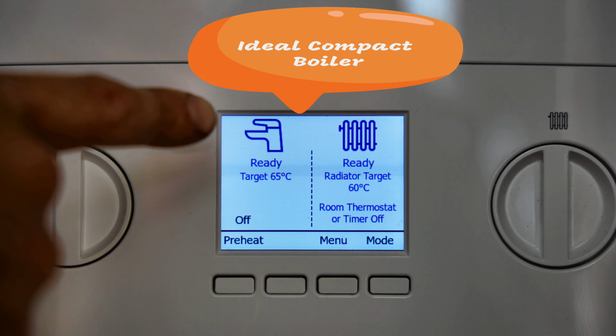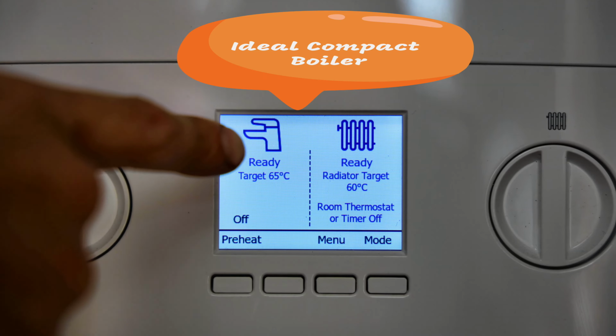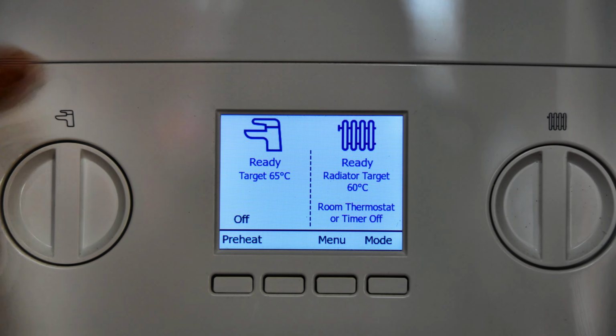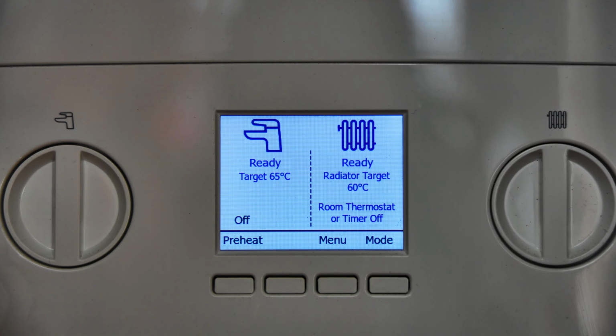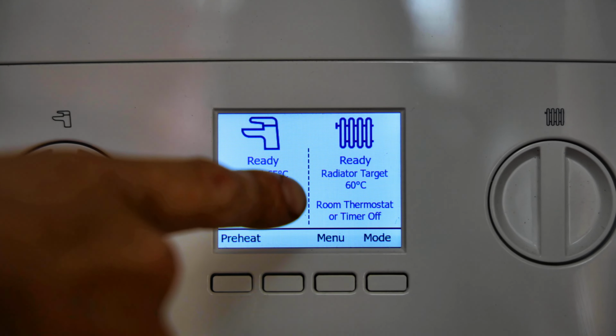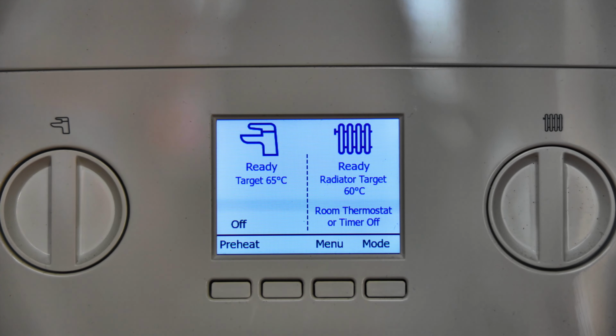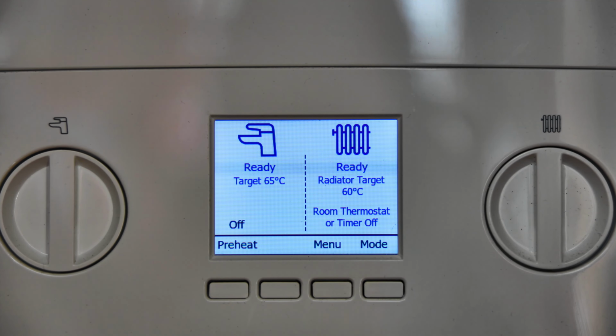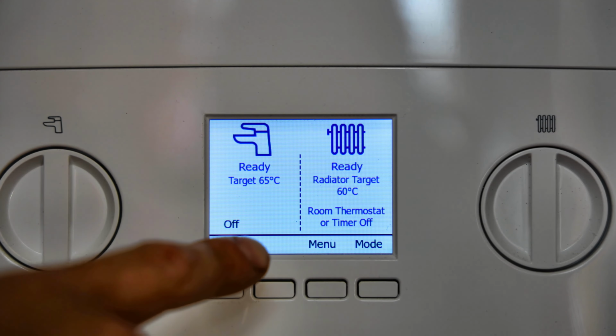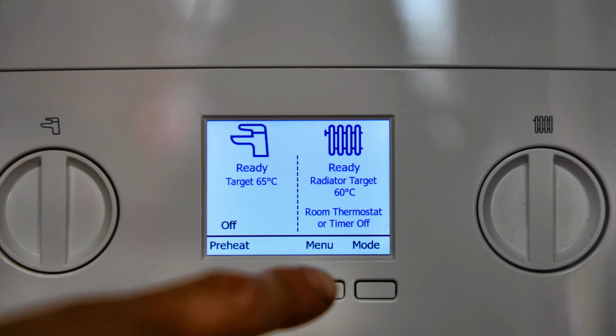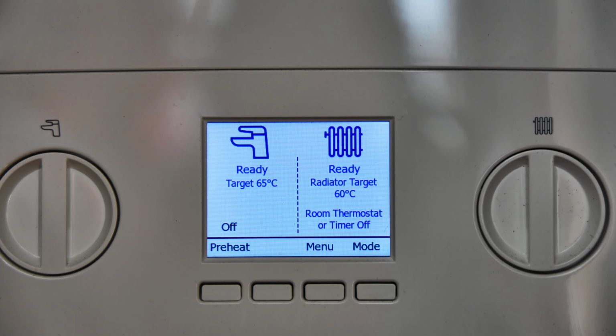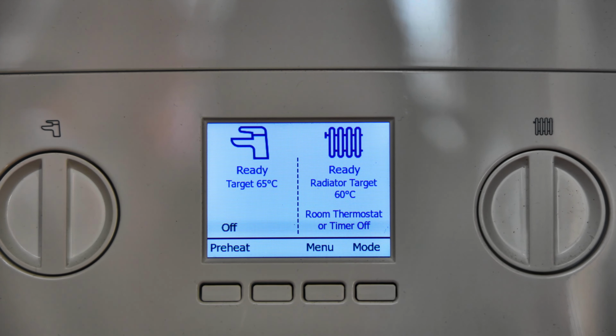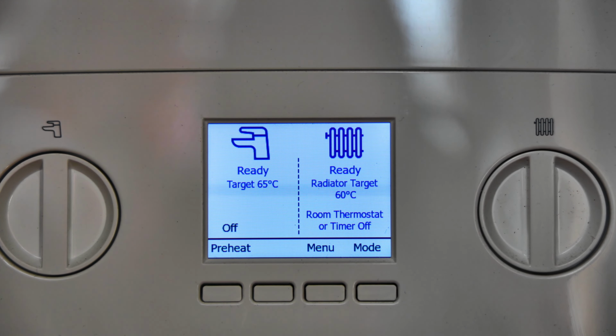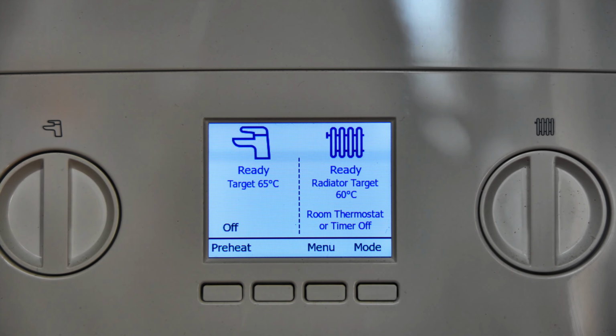And then on the right hand side, that's the radiator symbol, which says ready, meaning that the room heating at the moment is off. And then the radiator target temperature is 60 Celsius. So that's actually the temperature of the radiators, not the room. And you can see at the bottom it does say room thermostat or timer off. So if the programmer was on, that again would illuminate orange and say on, and then it would fire up and get the radiators to 60 Celsius.